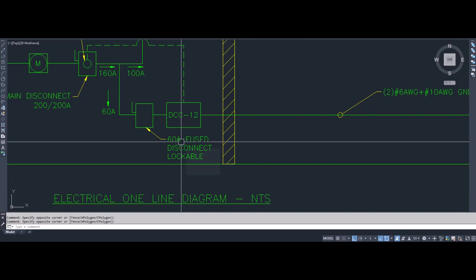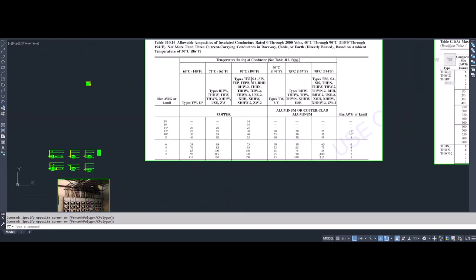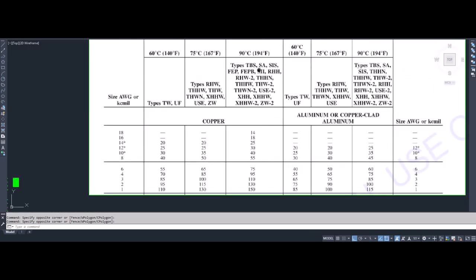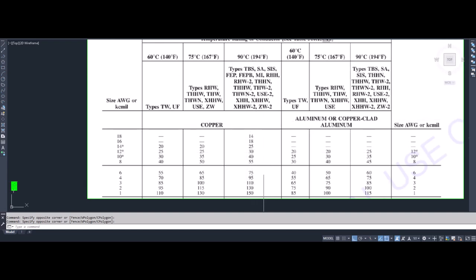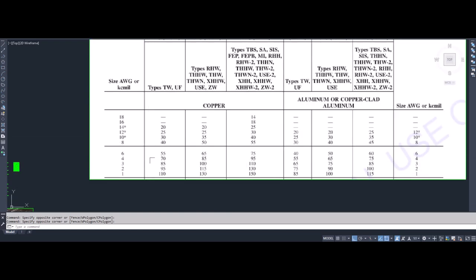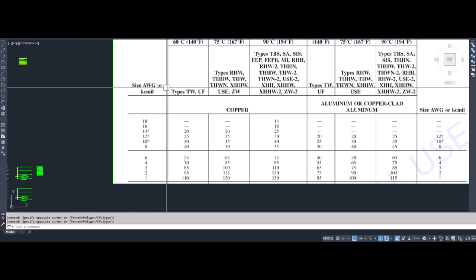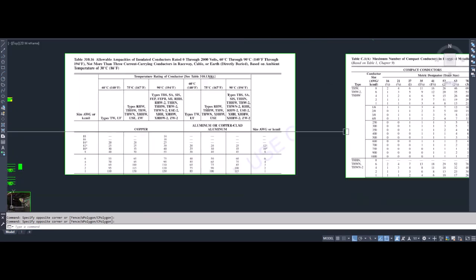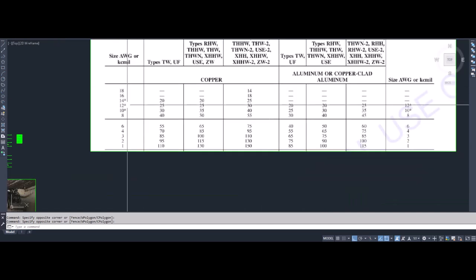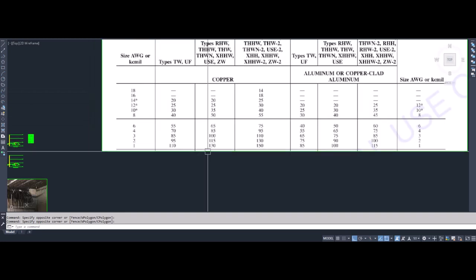If it's a 60 amp fuse, you go here, and this is the column that I typically use, the higher Fahrenheit. So basically this one, it allows for higher amperage. And for a 60 amp, you can see that it falls within this one here. So this number 6 wire can handle up to 75 amps. So you can use a 6 AWG wire size. And as you can see, as the wire gauge numbers go down, it's actually a thicker wire, right? That's why as the numbers go down, you can handle a higher amperage.